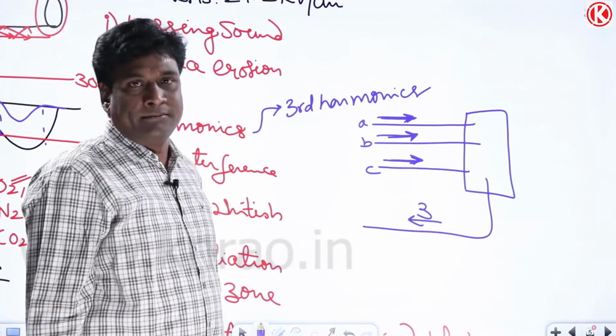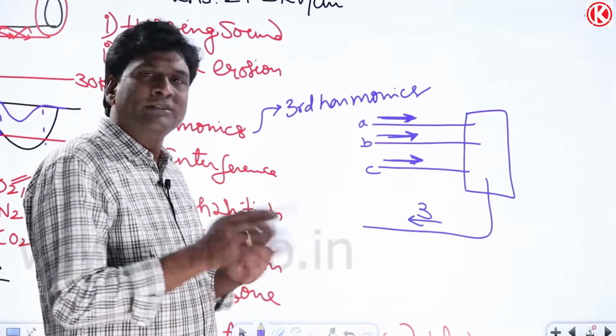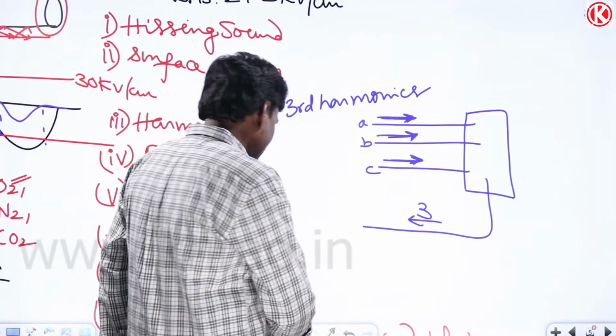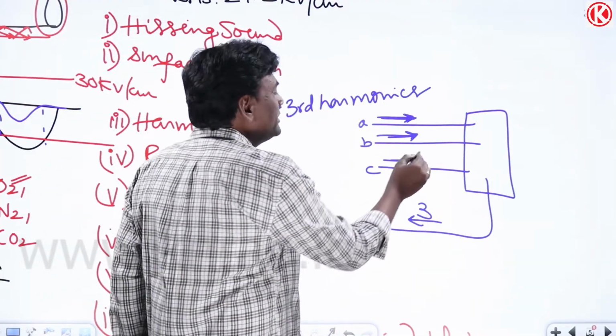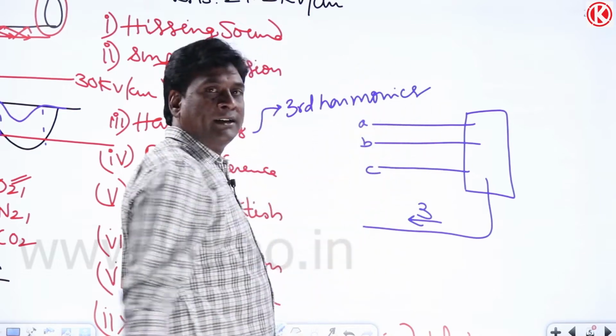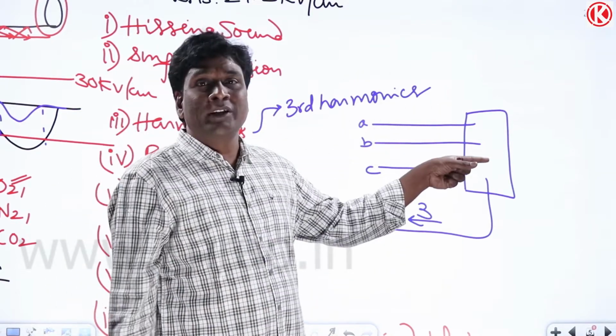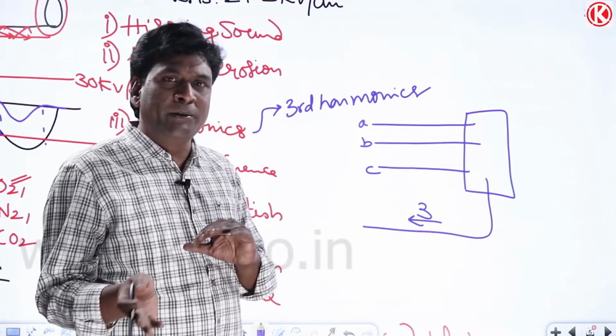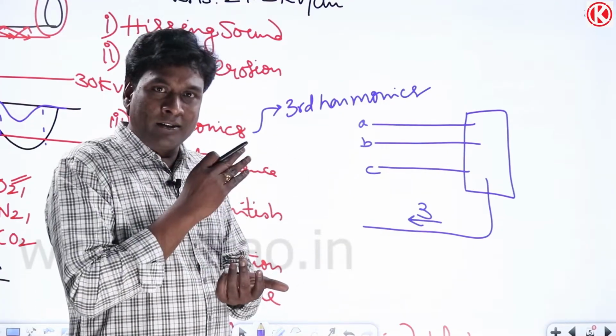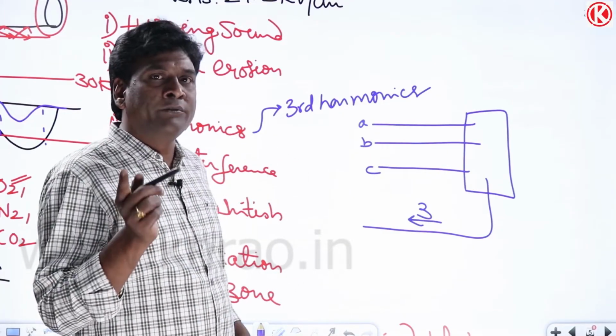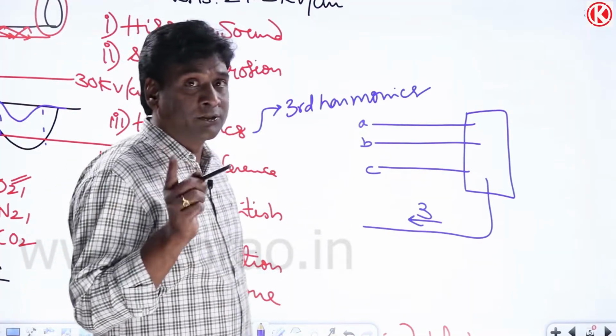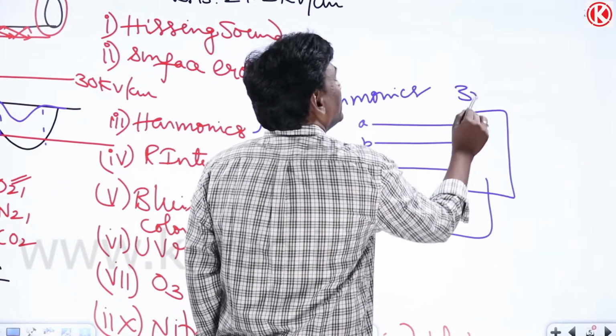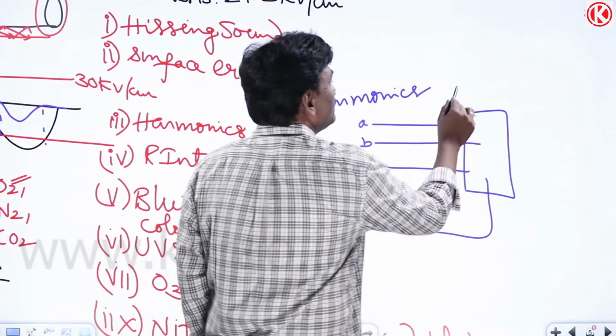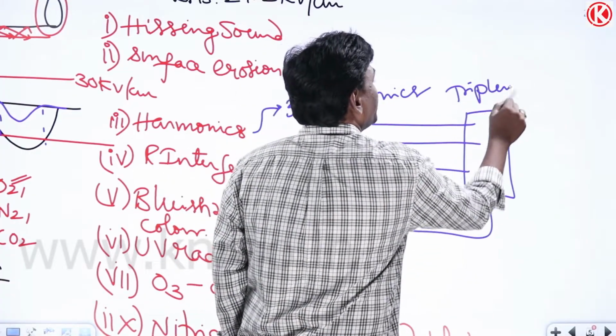If ground wire is not there, or if ground is not properly maintained, in that condition these currents cannot flow because the return path is not there. So because of lack of triplen harmonic currents, triplen harmonic voltage will be induced. If you want a clear picture about this, just go through the videos of transformer, three-phase transformer harmonics. So triplen harmonic voltage will be induced.